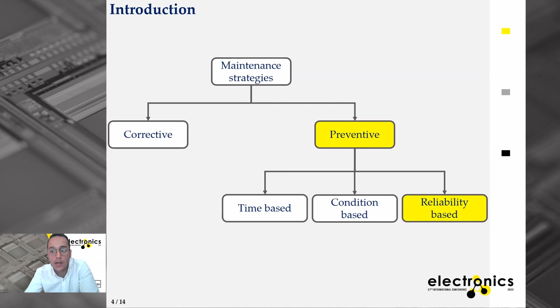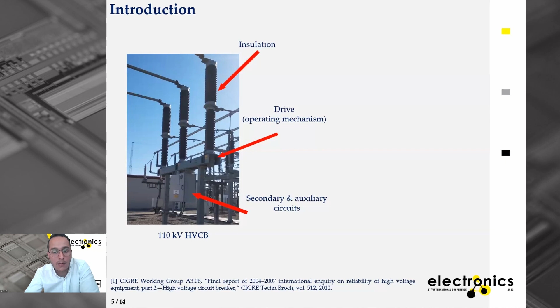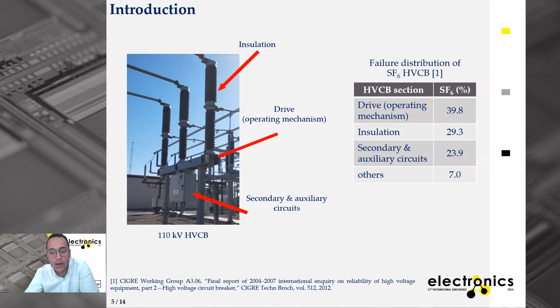So here is the figure for a 110 kV high voltage circuit breaker in the substation. As you can see, we have three main parts for the circuit breaker. We have the insulation medium, which in this case is filled with SF6 gas. Then we have the drive or operating mechanism, and at the end the secondary and auxiliary circuits. Based on the latest CIGRE statistics, which were published in 2012, for SF6 high voltage circuit breakers the main cause of failure is related to the drive and operating mechanism, approximately 40%. Then we have the insulation medium, and then the secondary and auxiliary circuits.